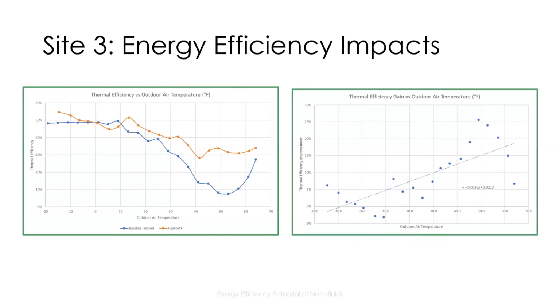And we were told by personnel familiar with the system that some radiant heating panels that were tied to the system were no longer active, and we assumed that this was accurate. However, based on these calculated efficiencies, as well as some subtle clues from the automation system, we have reason to believe that these heating panels were active for at least a portion of our monitoring period.